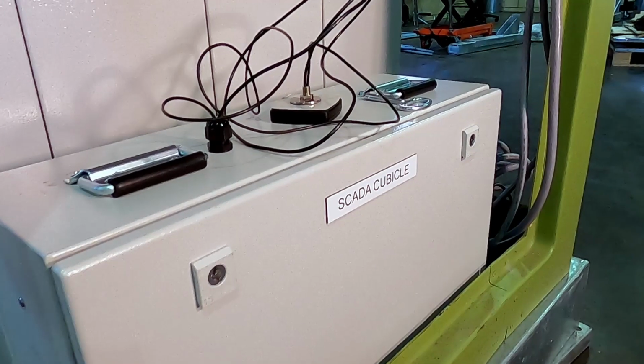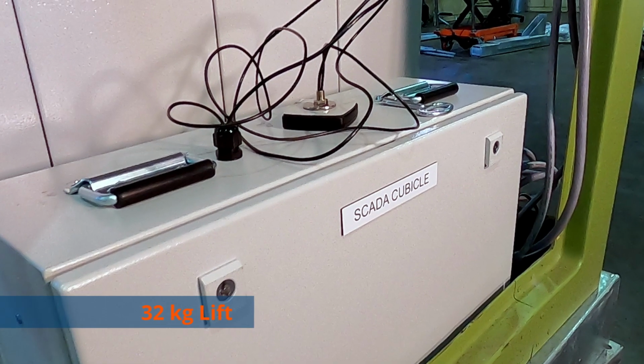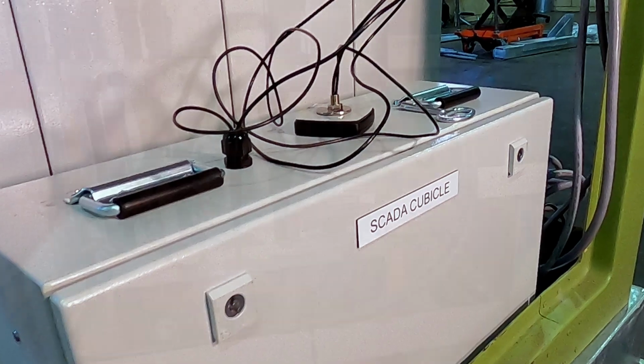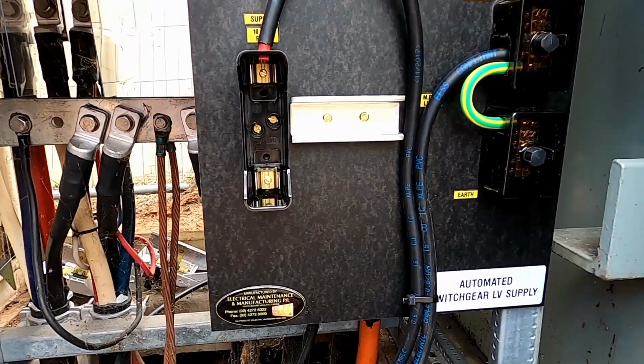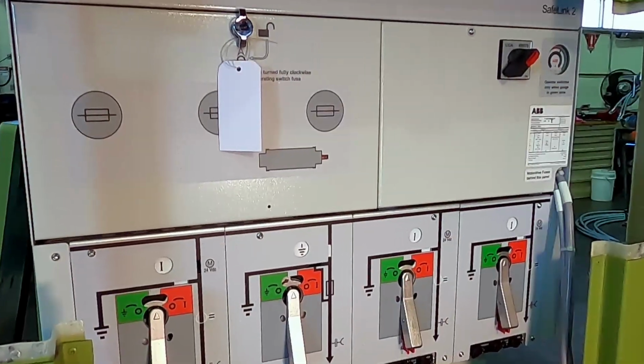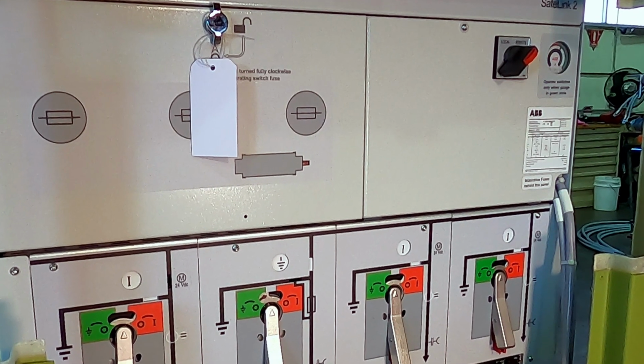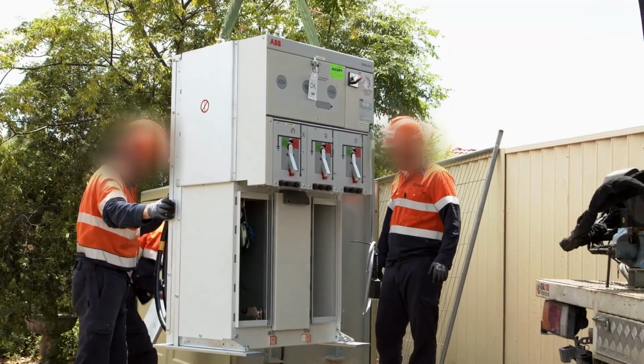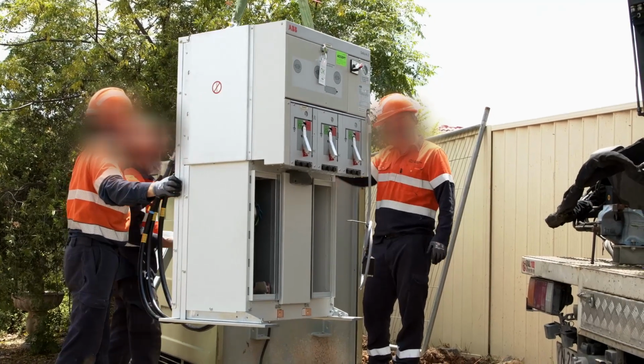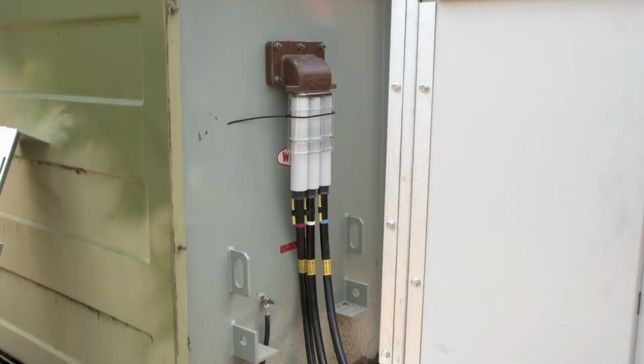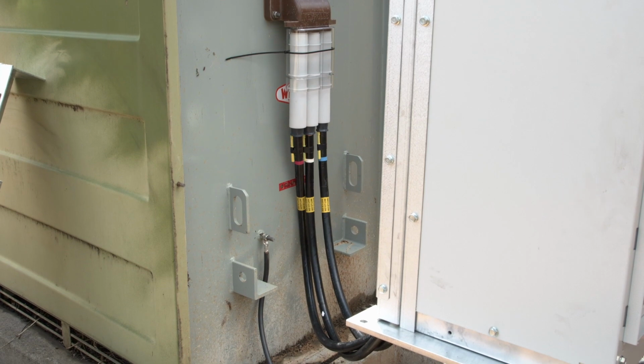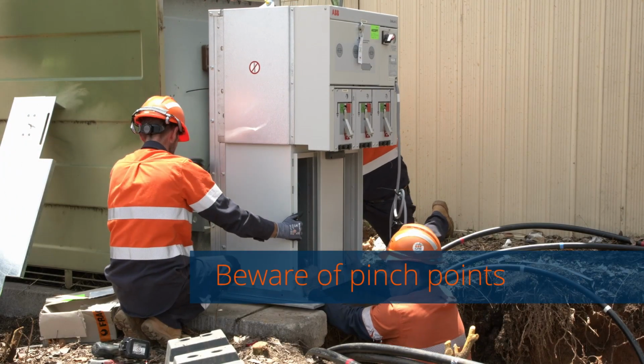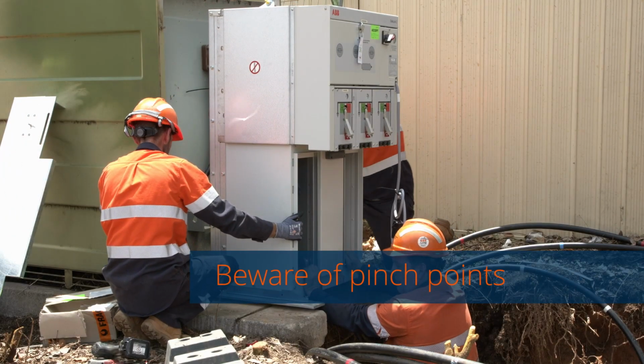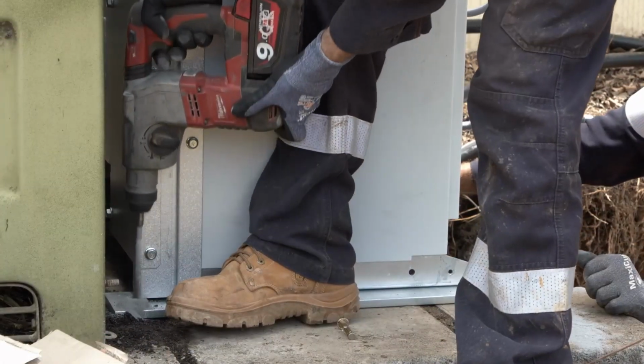The main components to be fitted are the SCADA cubicle with LV supply cabling, the switchgear LV supply panel, and the automated switchgear assembly, including SCADA cabling. The switchgear is moved into position by crane, close enough to the transformer to allow connections to be made. Once the transformer connections are complete, the switchgear can be landed into position and bolted in place.